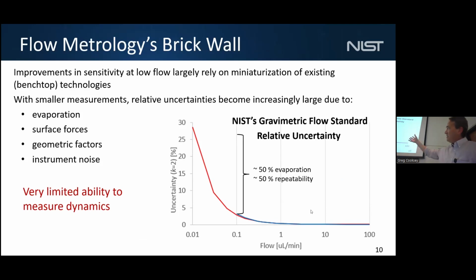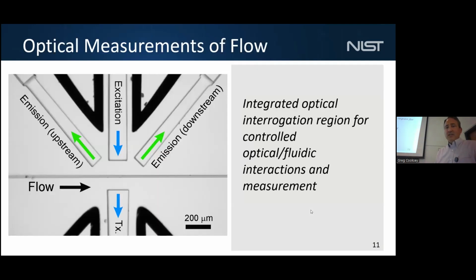And the other thing to think about here, too, is that the dynamics are really slow. At 100 nanoliters per minute, it takes 5 minutes to make one measurement. So you're not measuring anything dynamic. You're only estimating the average flow rate over that time. So our idea was to measure flow using an optical system. And this is where we come in with our microfluidics.